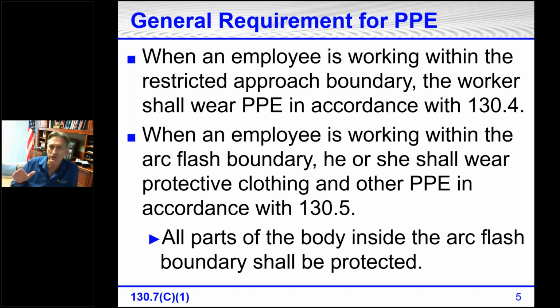We have certain restrictions before we cross a boundary. For example, crossing the arc flash boundary, we have to be wearing arc rated clothing and the proper arc rated equipment when we cross into the arc flash boundary. Before we cross into the restricted approach boundary, we have to be wearing PPE in accordance with the potential shock, the voltage level. We're going to look at that here as well.